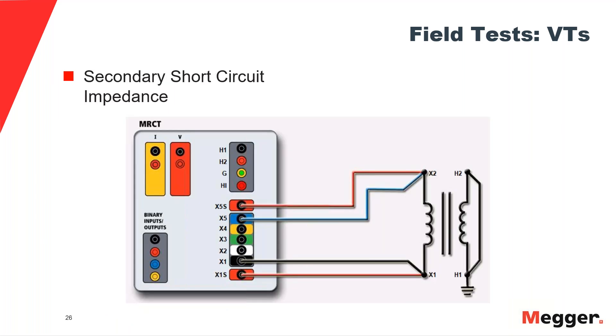Finally, the secondary short-circuit impedance measurement allows us to determine the copper losses of the VT and calculate certain parameters used to model the VT, enabling us to predict its performance in the field.